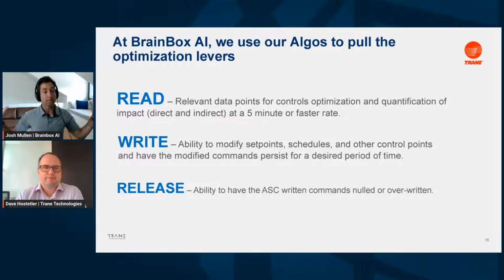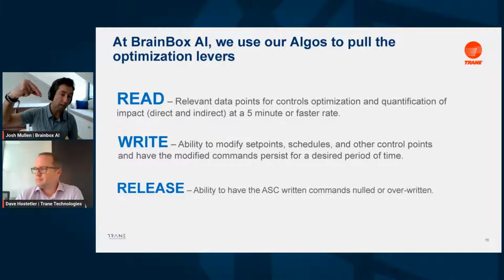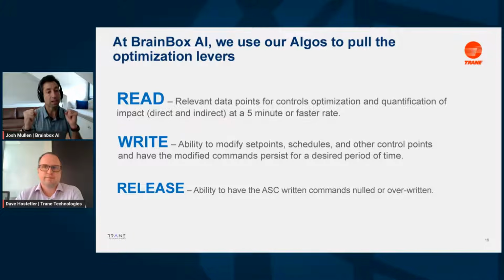All right, so regardless if you're communicating independent data layer or if we are connected onto your control network, for advanced supervisory control to happen, we need to be able to read, we need to be able to write, and we need to be able to release those writes. So for the reading, most advanced supervisory optimization platforms need to be able to read data every 5 minutes. Sometimes with chiller plants, it could be as fast as 1 minute.